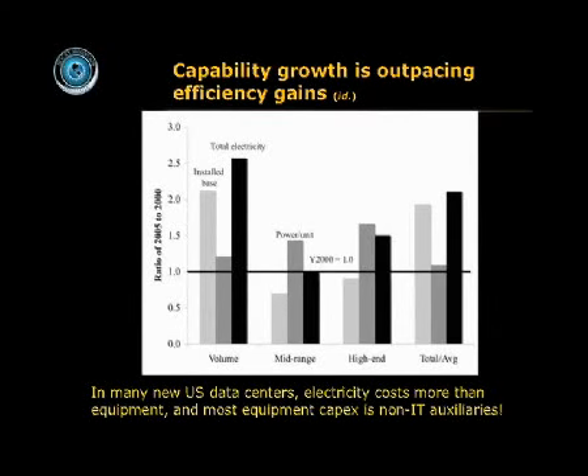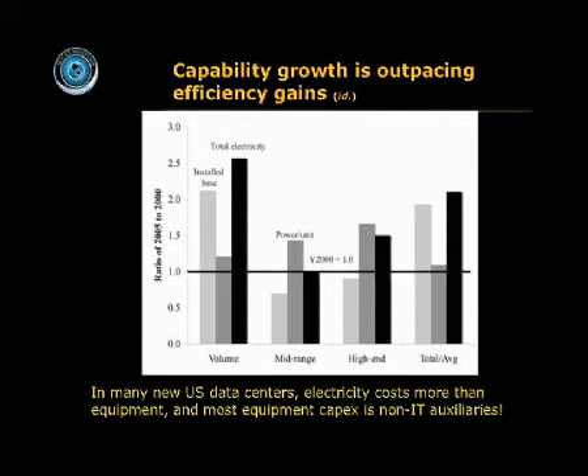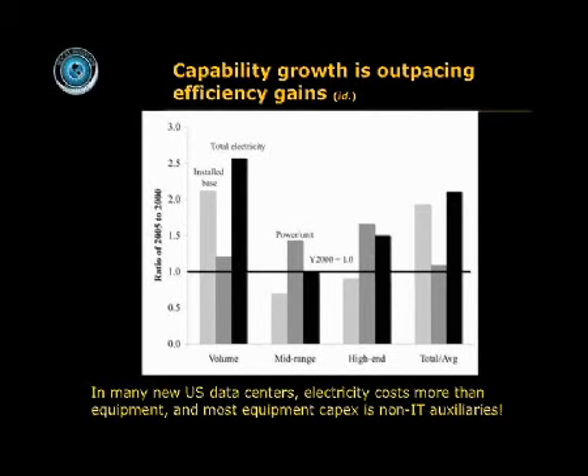In the data center business, if you compare, let's say, the United States 2005 to 2000, you find that the amount of data center base we have installed has more than doubled, but the electricity use has grown more than that, because the power per unit has been going up, mid-range and high-end. So in total, there has been some increase in the energy intensity. And in many new U.S. data centers, the electricity costs more than the equipment, and most, even 3/4 of the equipment capex is not for the servers, not for the IT equipment, but for the cooling and power supply.